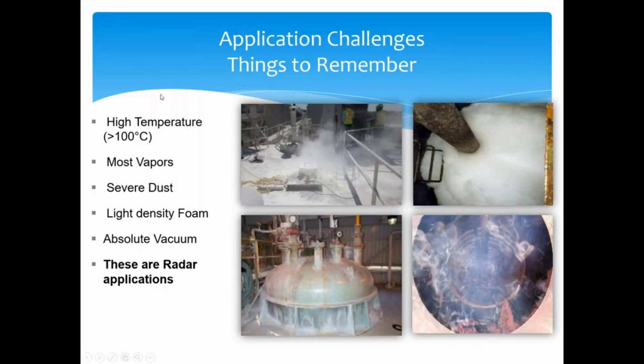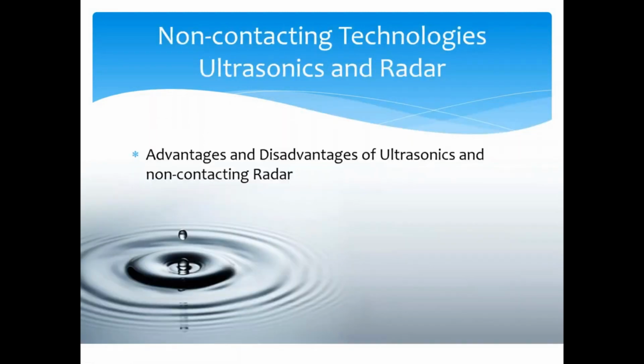Anytime you start getting temperature gradients or high temperature, you're going to want to look at radar. Again, that's because speed of sound through air is affected by temperature. Radar is not affected by temperature or by pressure. So if we're dealing with high temperature, changes in pressure, or vacuum, these are radar applications. If we're dealing with vapors in the headspace, dust, or foam, specifically low density or medium density foam, again, straightforward radar applications.